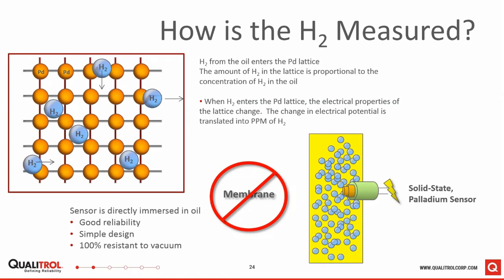So this is a real benefit, because traditionally, measurement of gas in oil, either in the lab or in the field, has always involved extraction of the gas from the oil prior to measurement. And most of the other Qualitrol products do require gas extraction prior to measurement. Typically, this is achieved using a membrane or a headspace extraction system. But generally, it's not a bad thing. It introduces complexity to the system. And in fact, for these type of single gas applications, membranes can introduce some variability into the analysis, and they can potentially be a weak point in the physical structure of the monitor.